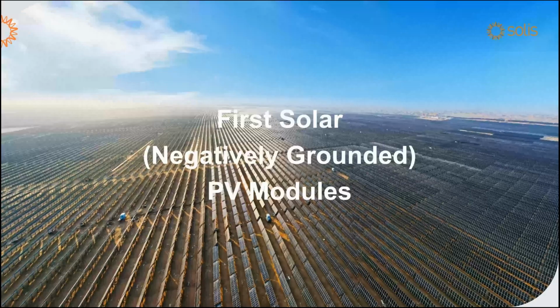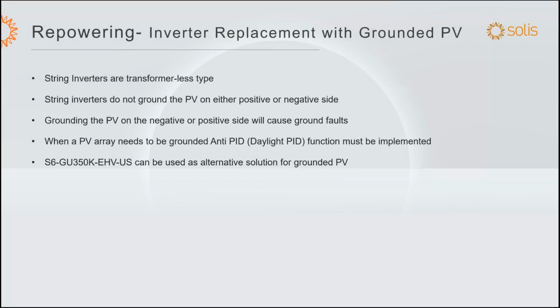Another challenge is the negatively grounded system. Most negatively grounded systems could also be floating systems with an anti-PID recovery option, but some PV modules, like First Solar PV modules, require or must have a negatively grounded PV. So the floating system or PID recovery is not an option in this case. With First Solar modules, string inverters are transformerless, so grounding the PV positively or negatively is not an option, and it will cause a ground fault. When a PV array needs to be grounded, the anti-PID daytime PID function must be implemented.